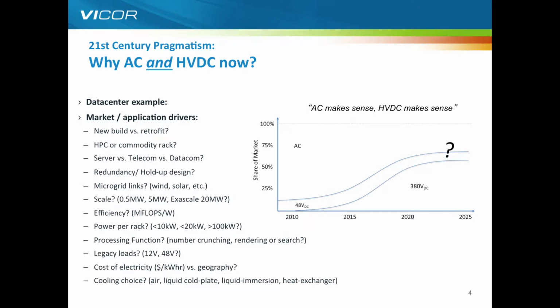We've got installed bases. For example, at Vicor we have two main sites, with small data rooms at each location, I wouldn't call them data centers. Right now they run on an AC power outlet, and due to the small size, it wouldn't make commercial sense to tear up that AC system and put in a DC one. However, if you're building a new office block, school, library or factory from scratch, now is the time to consider 380 volts DC from the start, and you can plug in your 380 volt DC server. So there are lots of different choices and conditions that need to be met before we can decide whether AC or high voltage DC makes sense.